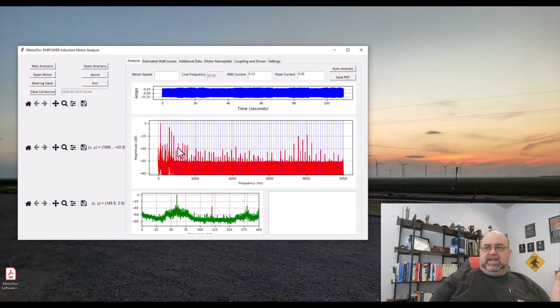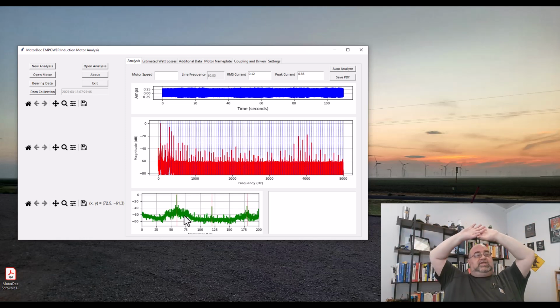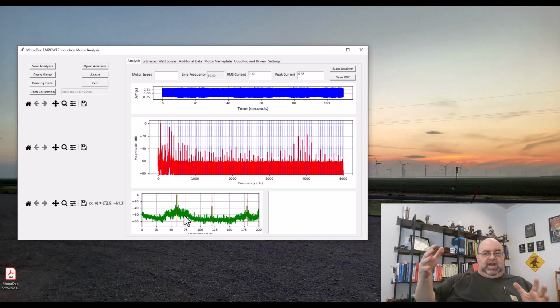Do I trust this data? Does this compare to the other one that we did? No, there are extra peaks in here and everything else from other things in the area, including another machine running right next to it that's radiating off its surface, lighting systems, HVAC systems, all kinds of moving components, all of which are causing the surface of the machine to have an antenna effect. So the ground is somewhat close, and I shouldn't see this on there. I should see a dampened version, just like you saw with the one back here. But I'm running loose conductors inside conduit, so I should be expecting things to go wonky.